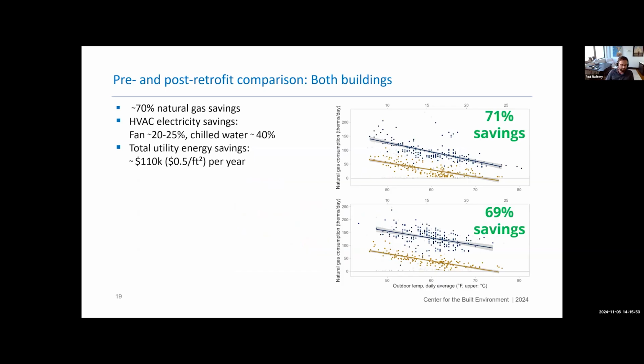And because this is the natural gas meter data for the building, this is a 70% scope 1 emissions reduction on site, which you can't achieve by almost any other means, right? We didn't electrify anything. We just leveraged an existing plant replacement, and we were able to reduce the scope 1 emissions by 70% in these two buildings. There are also HVAC electricity savings. So we saw about 20 to 25% fan energy savings and about 40% chilled water savings.